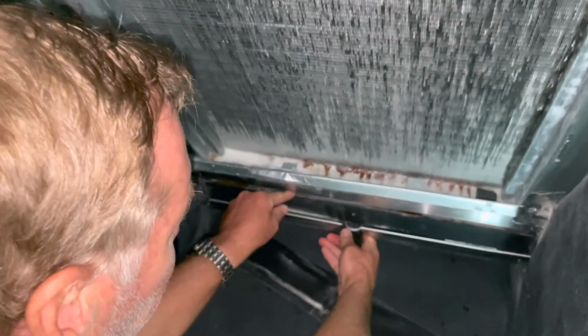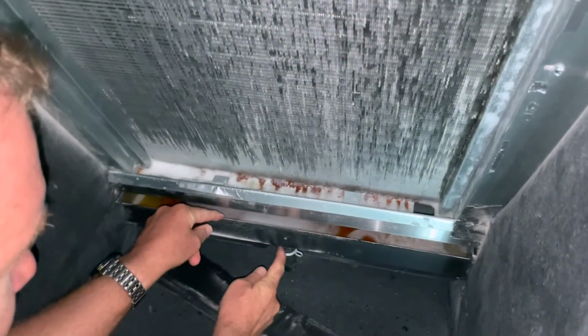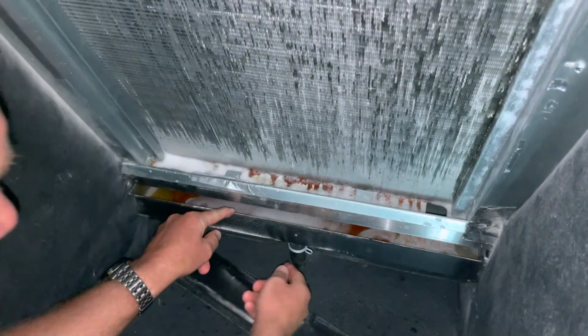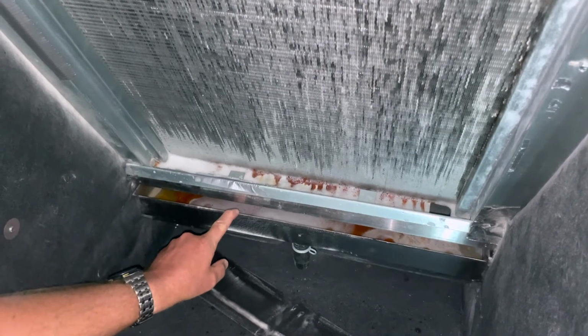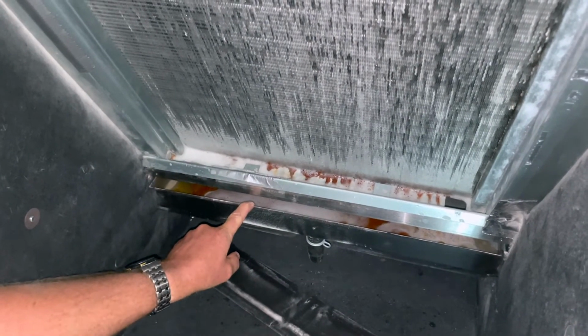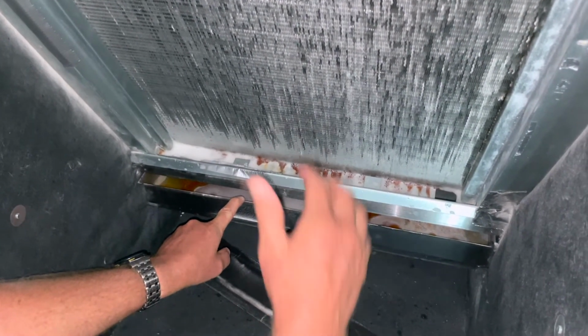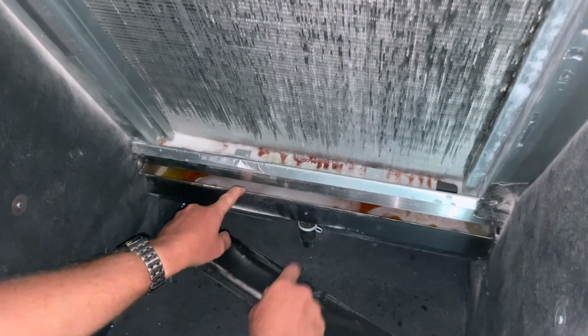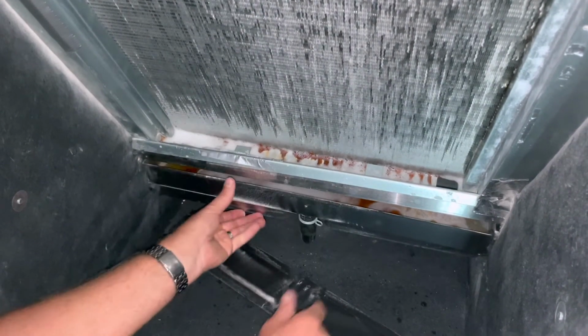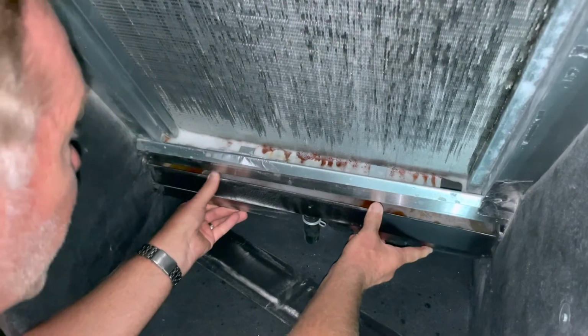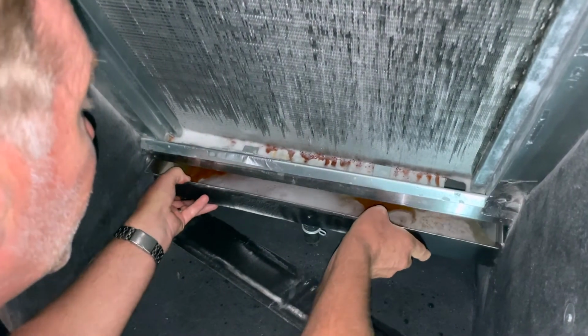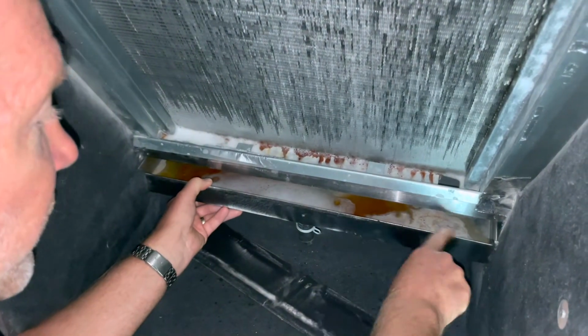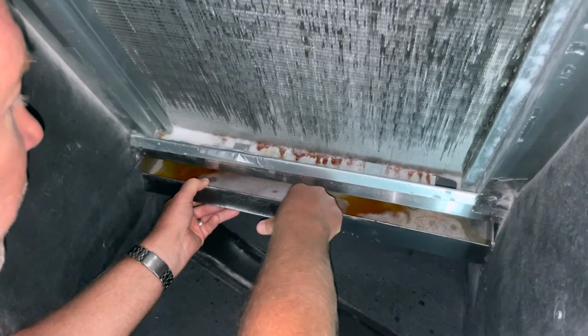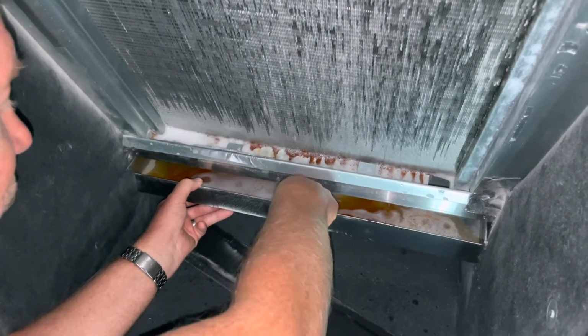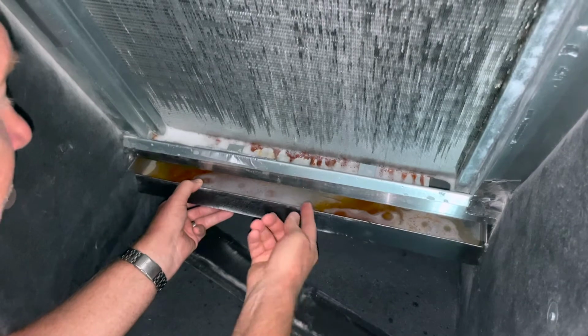Here's your drain pan, connected to this drain hose. All ACs produce condensation that has to go somewhere, so it drips down into this pan and out through this hole. We want to check that there's good drainage from the pan—there's some water in there, which is fine, but you want to make sure that hole stays clear.